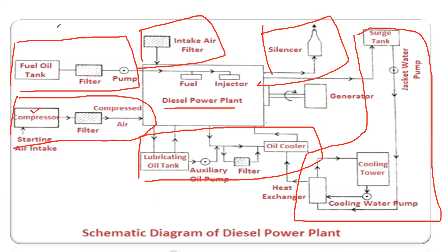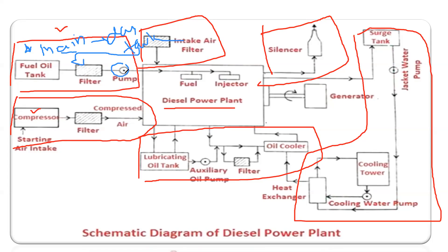First thing is your fuel oil tank. In the fuel oil tank, there are two types of tanks: the first one is the main tank, and the main tank gives oil to the day tank. After the day tank, it passes through the filter, because the filter reduces impurity. When oil passes through the filter, it is directly connected to the pump. The function of the pump is to inject the fuel with high pressure into the diesel engine.